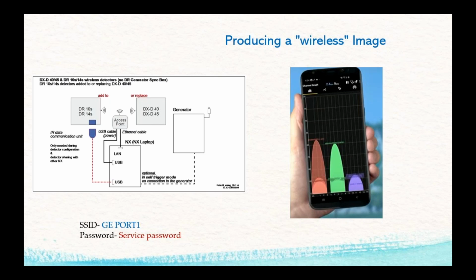So we go to the computer when we're installing these digital panels, and we give it an SSID and a password, just like when you go into Walmart and you can't get on their Wi-Fi because they've got it locked down with a password. Same thing we do on these, and we call them the panels. If you have 3 rad rooms all in a line, how do we keep that panel from sending an image to the other room? So it has a different SSID and password, and the frequencies and the channels are changed just to make sure that panel talks to that piece of equipment. No sending images across the hallway or whatever.